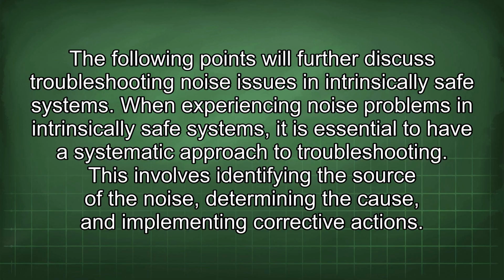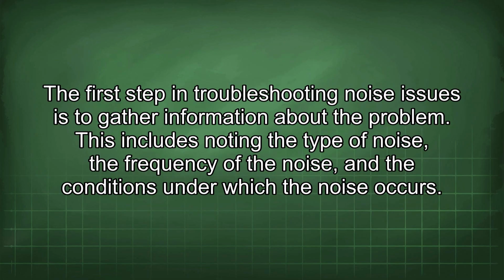When experiencing noise problems in intrinsically safe systems, it is essential to have a systematic approach to troubleshooting. This involves identifying the source of the noise, determining the cause, and implementing corrective actions. The first step in troubleshooting noise issues is to gather information about the problem. This includes noting the type of noise, the frequency of the noise, and the conditions under which the noise occurs.